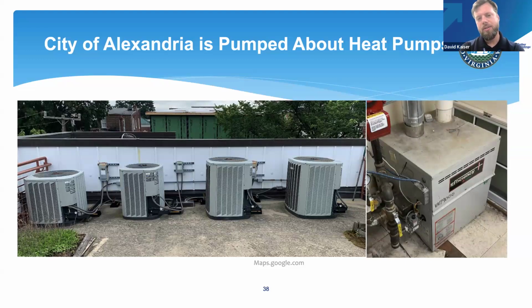So one of the exciting things about this is that we have two distribution systems. We have a refrigerant line system providing cooling to those apartment units, and then we have a hydronic boiler system. And because these are old buildings, things eventually break down and get changed out, and the boiler is breaking in this specific instance. What we're going to do is get rid of the boiler and change these air conditioner units to heat pumps.